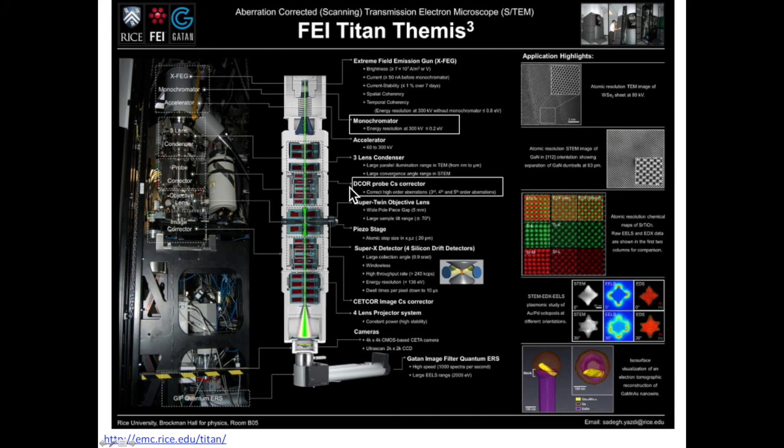The probe corrector sits between the condenser system and the objective system. You turn on the probe corrector when you do the atomic level STEM, the scanning transmission electron microscopy. The image corrector sits between the objective system and the projector system. You turn on the image corrector when doing the hi-res TEM to minimize the delocalization. Because there are two CS correctors in this TEM, it is also called the double-corrected TEM.